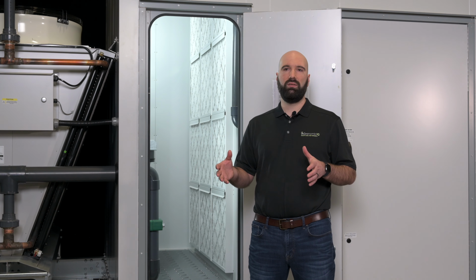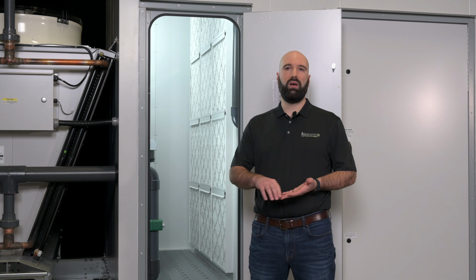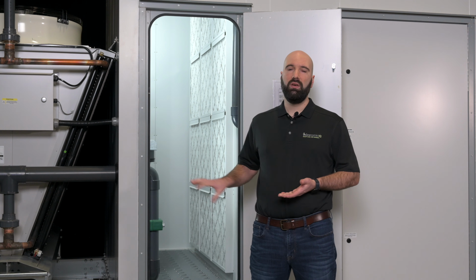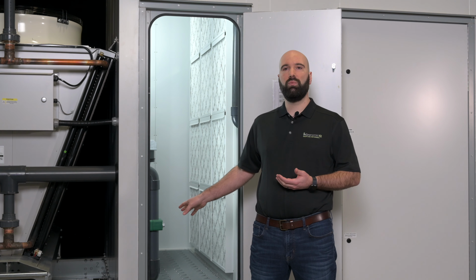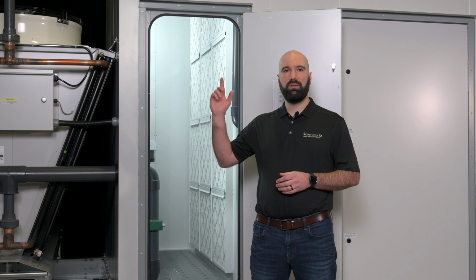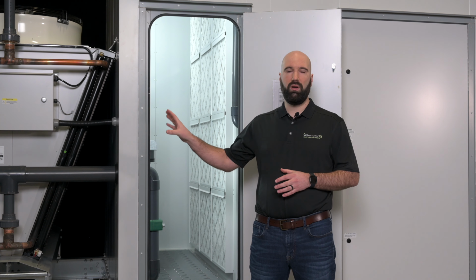In this first section of the air path through the unit, and that's how we're going to do this explanation of our technologies, we're going to follow the process air through the unit. This is the return air section. So this is where hot, humid air is coming from your space and is eventually going to be filtered, cooled, dehumidified, and then moved back into your space. This first compartment here, you see a bottom return air opening. So this is a unit that's designed to be on the roof. Again, that return air opening can be left, right, top, or horizontal if the unit's not packaged.